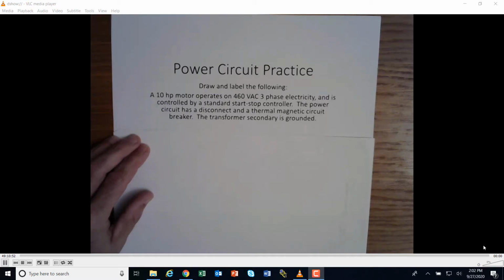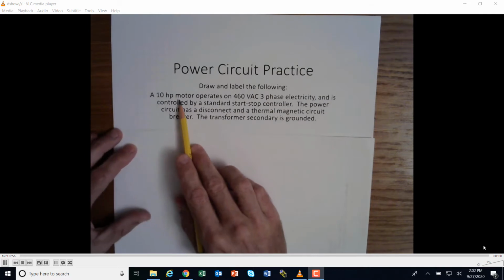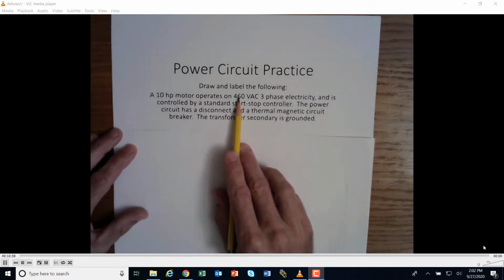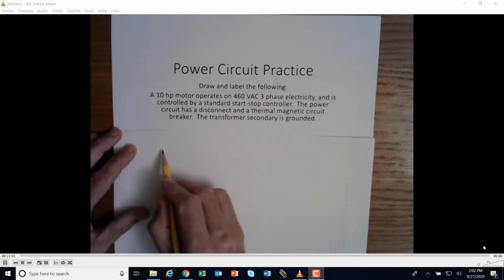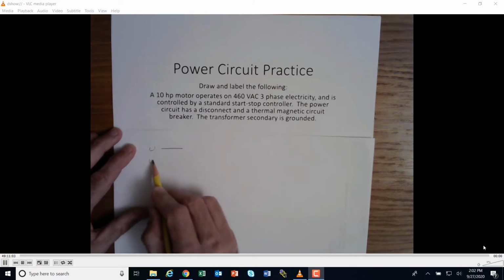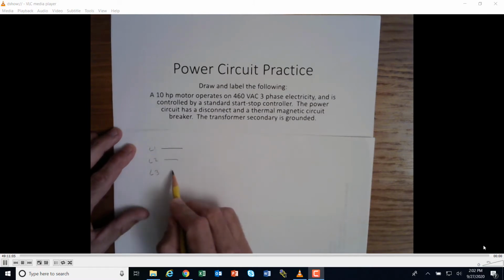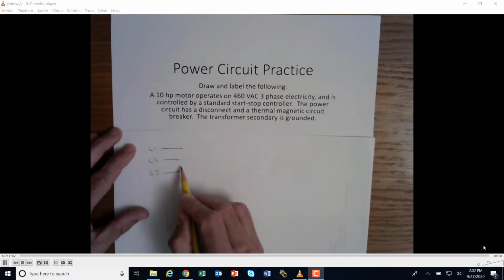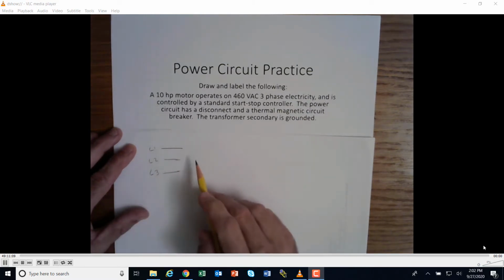Let's do a little power and control circuit practice. So we have a 10 horsepower motor, and it's at 460 three-phase. So I'm going to start up here with my power circuit with line 1, line 2, and line 3. Okay. So now this is going to have some type of disconnect or something on it.